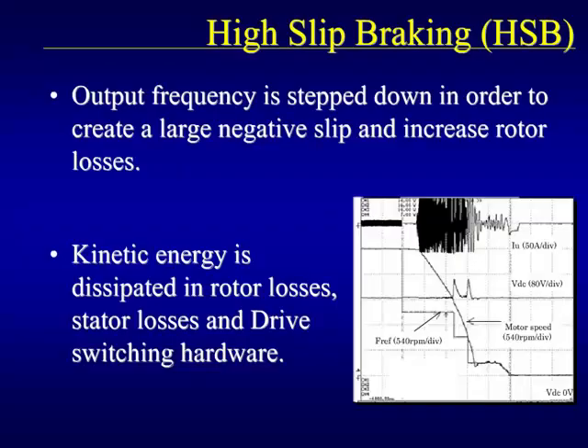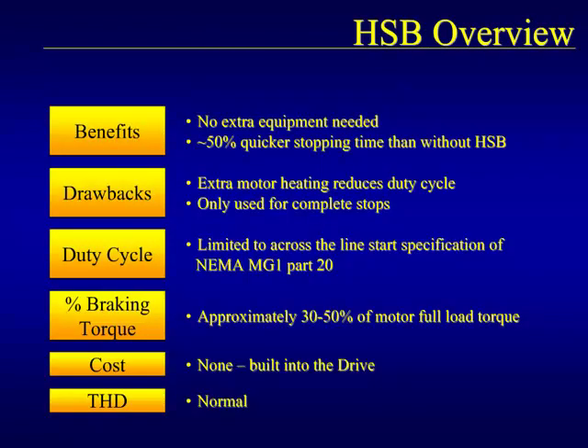High-slip braking is a braking method that uses an algorithm to maximize the motor losses during braking. Output frequency is stepped down at various intervals to increase the negative slip in the motor. This large negative slip causes the motor to act as an inefficient generator so that during regeneration, all of the regenerated power is dissipated from the motor itself due to its own inefficiency. High-slip braking is an excellent selection for large inertial loads — no extra equipment is needed and it can provide stopping times approximately 50% faster. Case studies have shown stopping times can be even faster than 50%, resulting from increased braking torque. The major drawback is the increased motor heating, as the majority of the energy is transferred into motor heat.